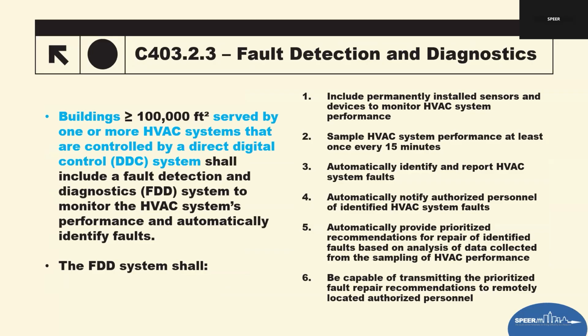The 24 specifically expands this section now in the requirements. Designated in the blue section here, it says any building 100,000 square feet or larger that has one or more HVAC system controls that are controlled by DDC must now include an FDD system. It's all acronyms, so it's fault detection and diagnostics. This is a major expansion compared to past versions, which basically only applied the FDD to certain types like packaged rooftops. So for a refresher, DDCs are the type of controllers that control and monitor analog and binary data. We just talked about that.